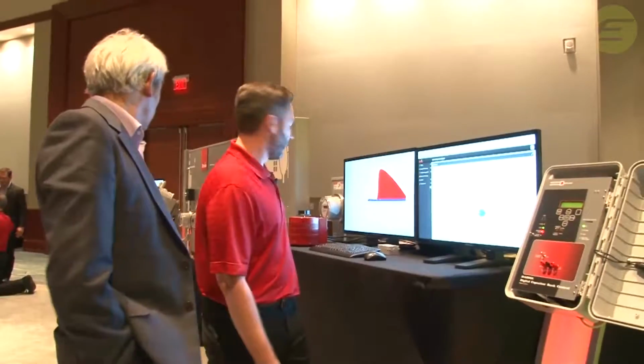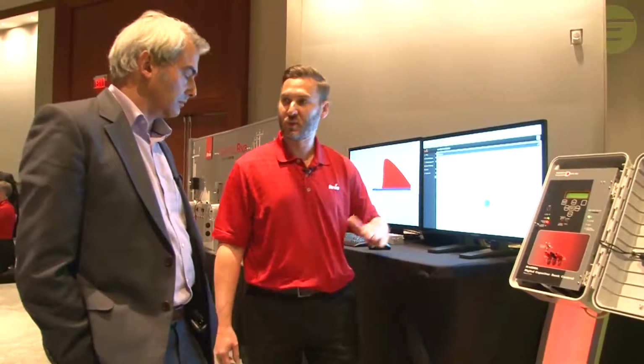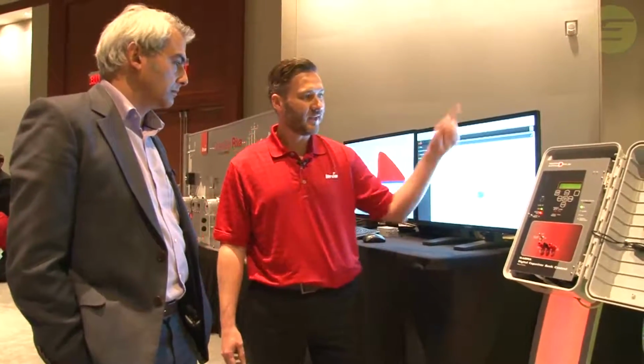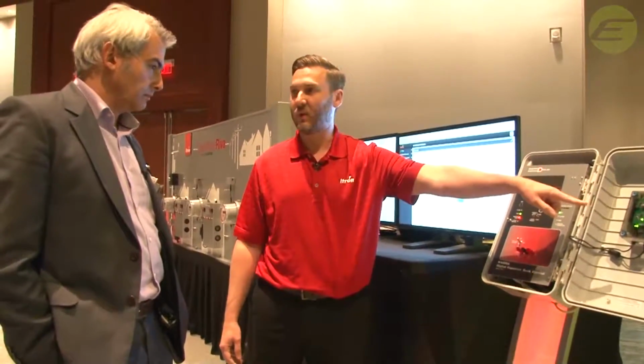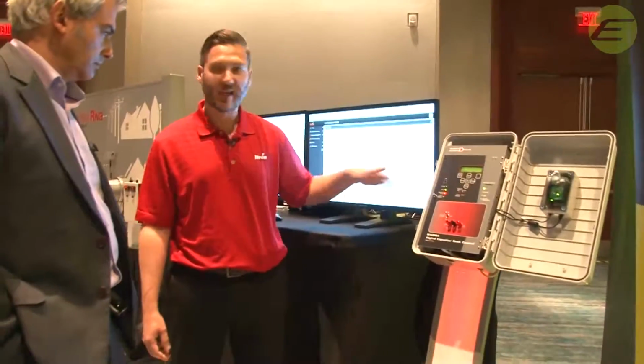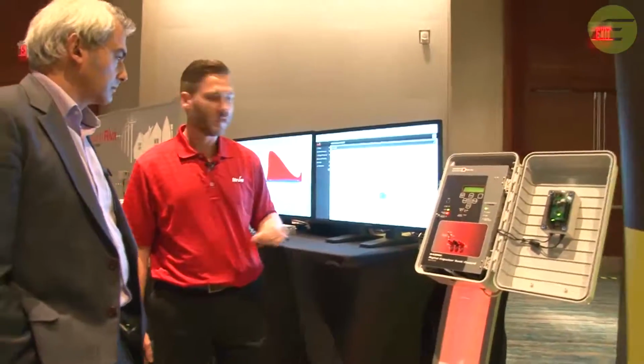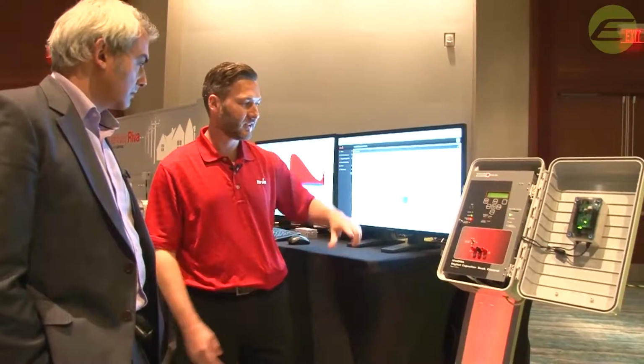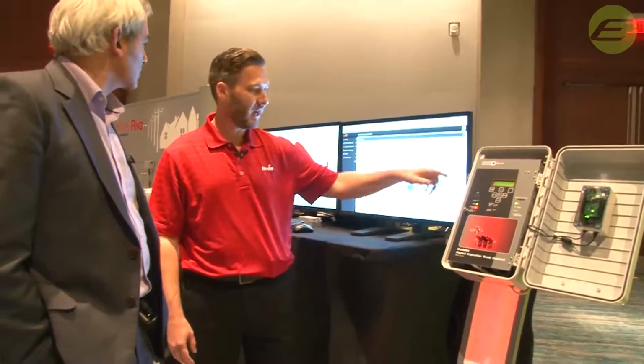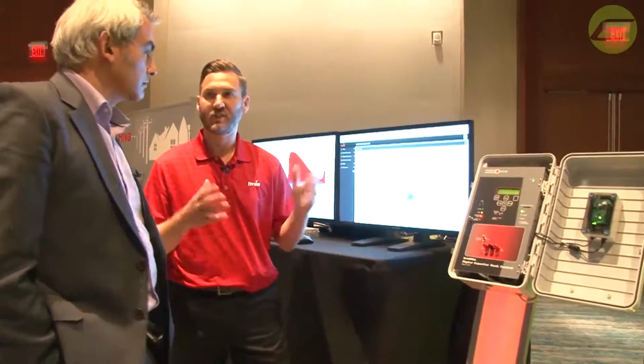And over here, when that realizes it's fallen below threshold and needs help to restore proper quality, it sends a command over to our DA gateway, but then through Modbus, a legacy sort of DA protocol, tells it to close in. And then we get a status update in the back office. I restore the voltage with the Variac, and it opens back. And it's just automated. Again, another example of edge intelligence without any back office permission.